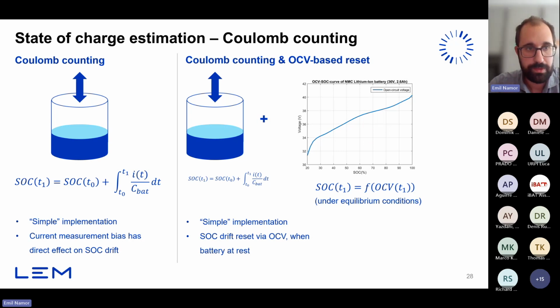The slightly more reliable method for state of charge computation is using coulomb counting plus a reset of the state of charge value from time to time, based on the relation between open circuit voltage and state of charge. This also remains relatively simple, but requires that a moment to do this reset based on the open circuit voltage is available, which is not always the case.